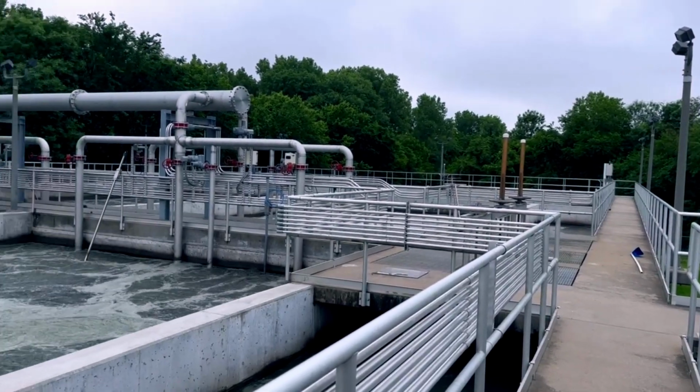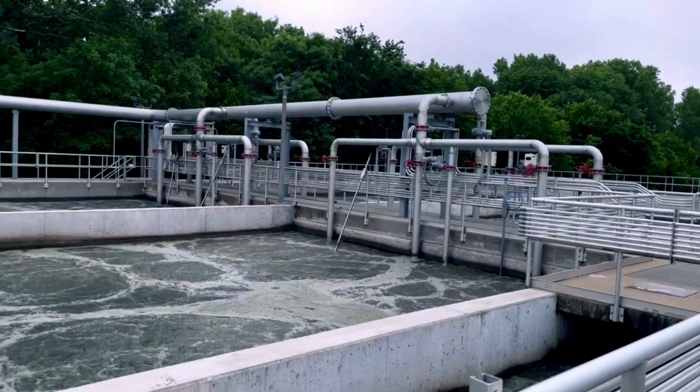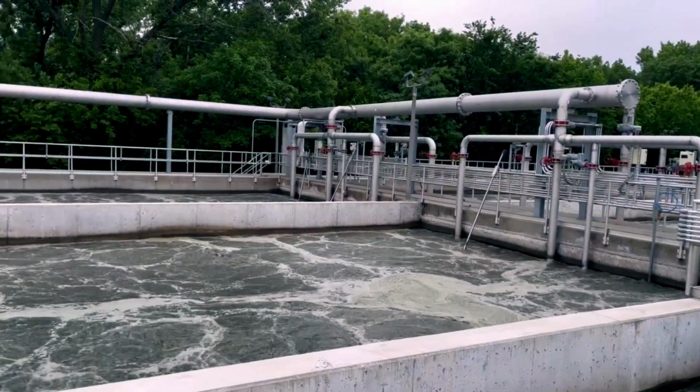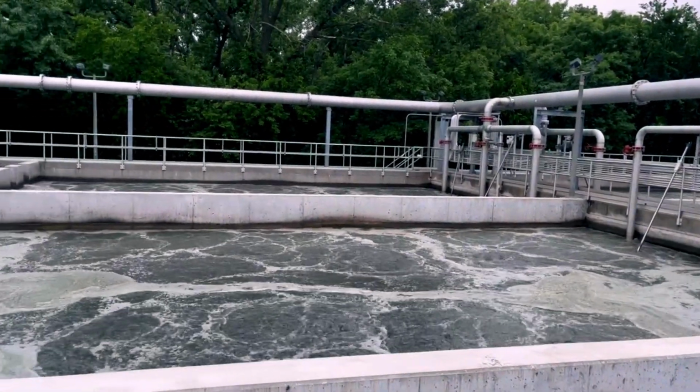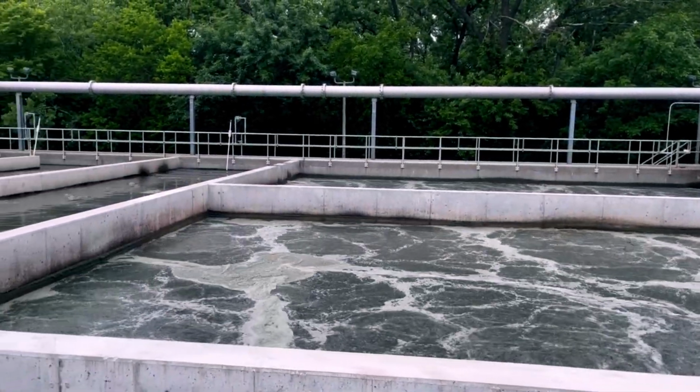The wastewater then moves to a deox zone, designed to provide time for dissolved oxygen to dissipate prior to running the internal recirculation back to the anoxic zone. The wastewater that is not returned to the anoxic zone falls over a gate and goes on to the clarifier.